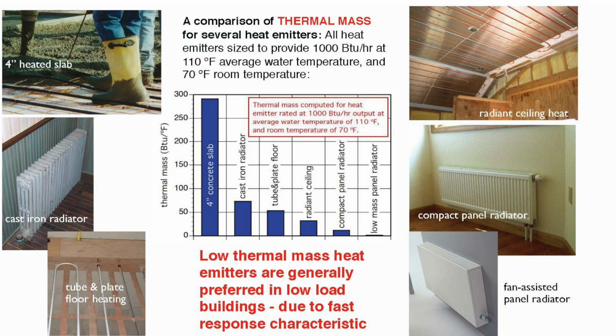Thermal mass on heat emitters. There's a huge range. As you'd expect, the slab is a very high thermal mass relative to the other emitters there. The fan-assisted panel radiator there in the lower right is about 1% of the thermal mass of that slab. Why is that relevant? Response time. Low energy buildings, as I mentioned, internal gains can make things change quickly in terms of temperature. You need systems in a building like that, especially where there's going to be significant solar gain or people gain, heat gain from people, lights, equipment. You need systems that can adapt quickly to that. They need to be able to turn off the heat as fast as you turn on the heat. Otherwise, you're going to get into overheating.